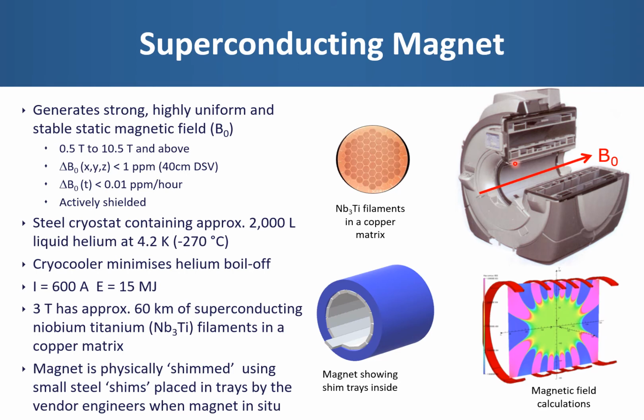As we've already mentioned, when the MRI system is installed, the service engineer arrives with a power supply and slowly injects current into these windings to ramp the field. A 3 Tesla magnet will typically require around 600 amps, providing a stored energy in the region of 15 megajoules. The power supply will then be disconnected, and since the windings have zero resistance, the current will continue to circulate indefinitely, providing the magnet remains superconducting. And that will of course generate our strong static magnetic field. The vast majority of MRI scanners, the permanent magnets and of course the superconducting magnets, are never turned off except in an emergency or for serious maintenance work.